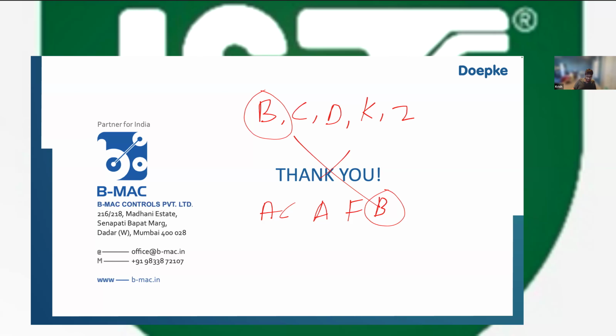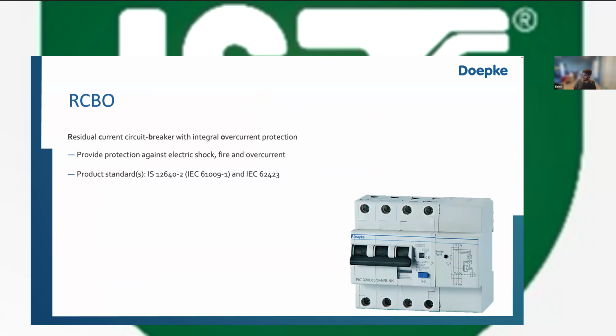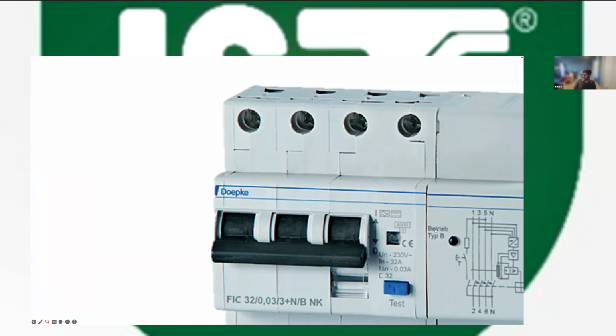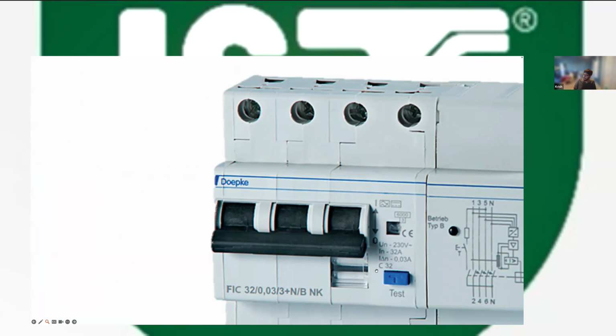And this gets even more confusing when we talk about RCBOs. Because if you see in this particular RCBO example, the RCD part of this RCBO is type B, but the MCB type of the overcurrent rating is type C. Now it may be type B here and type AC here. That does not mean that the overall RCD is a type B.